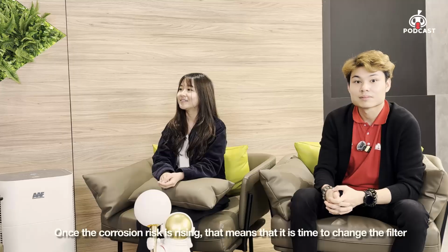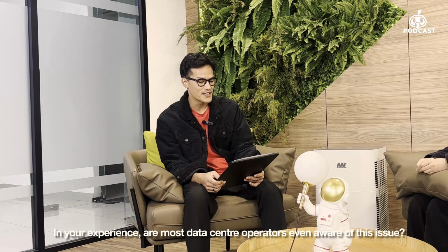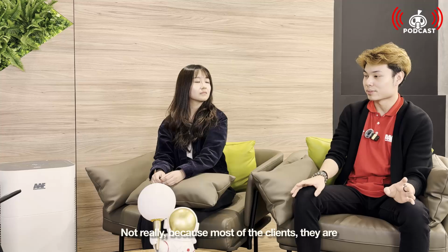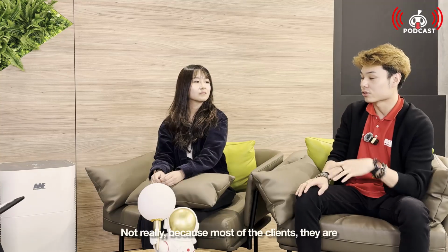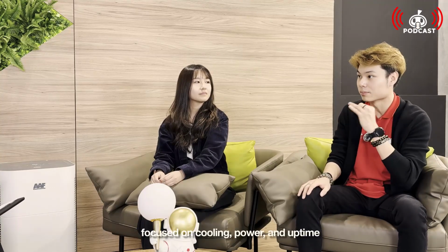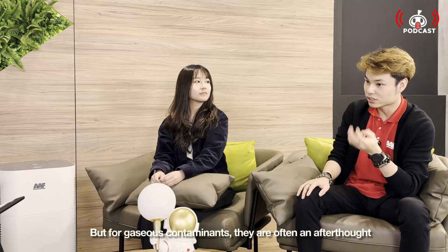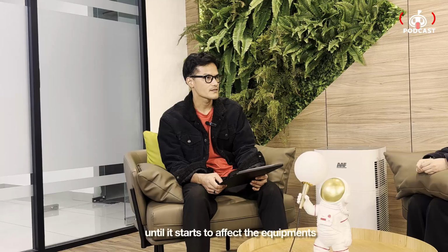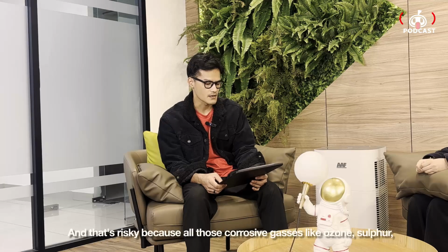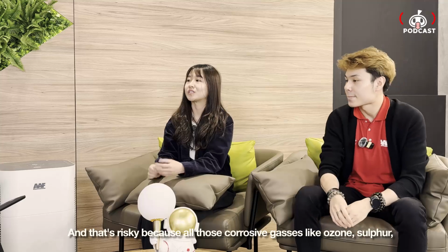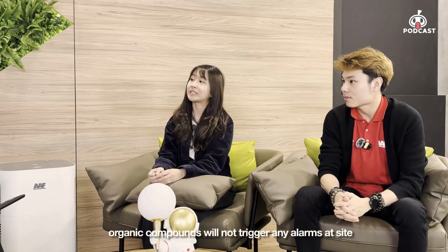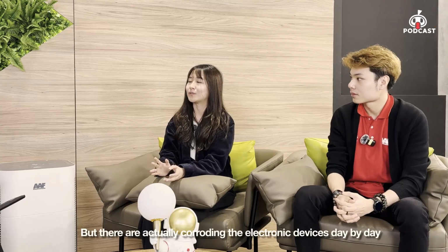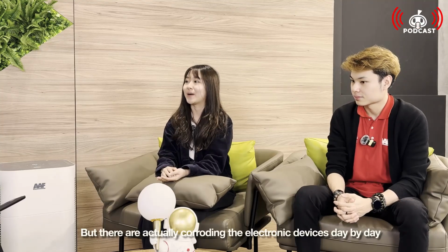All right. Okay, thank you guys. So guys, in your experience, are most data center operators even aware of this issue? Johan, not really, because most of the clients are focused on cooling, power, and uptime, the three main parts. But gaseous contaminants are often an afterthought until they start to affect the equipment. Yeah, and that's risky because corrosive gases like ozone or sulfur-containing compounds will not trigger any alarms on site, but they are corroding the electronic devices day by day.